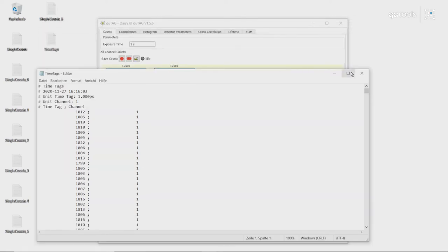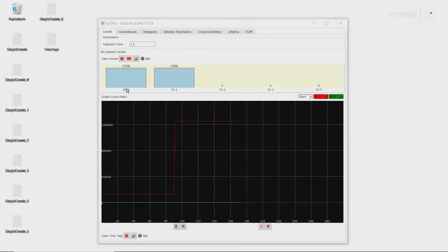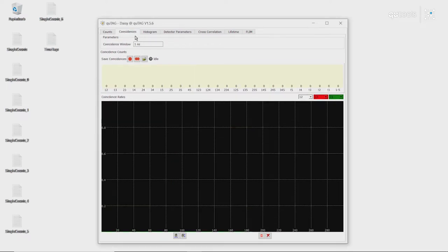As you can see, we have many events on channel 1, all around 1800 picoseconds. This is because the start channel is set with a cable that has a slightly shorter length than cable 1. So we have a slight time delay between the two channels.